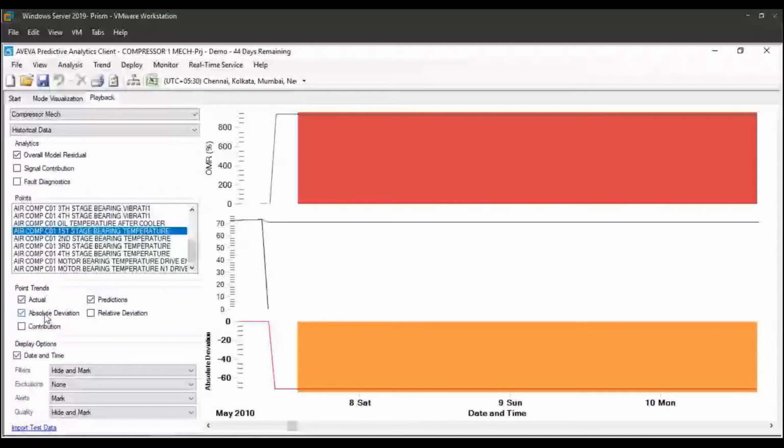And then that is indicated in the third graph over here. The yellow color over here tells me that the warning that I set for this particular variable's absolute deviation is giving me a warning sign. In that, if I take this particular time period of 8th Saturday, I see this around minus 65. So I've already configured it to show that this much range is in my warning area. So this is what I find out by analyzing each of those variables one by one.